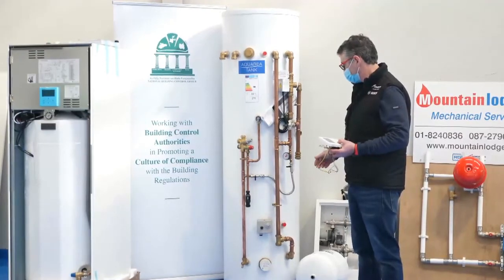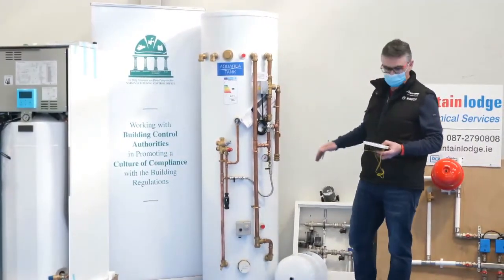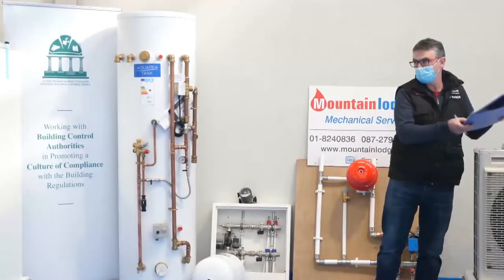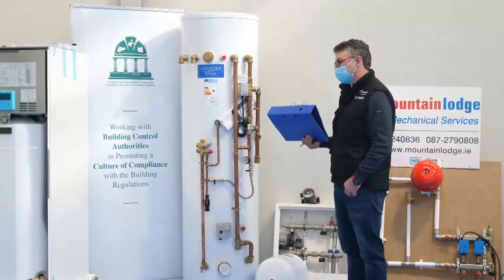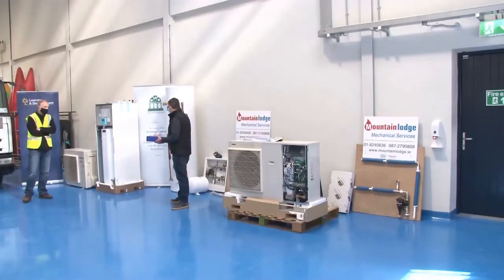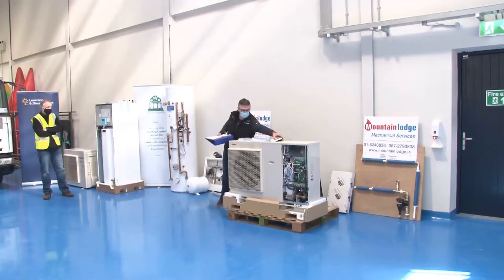And the second thing is there because we're heating hot water to max 52 degrees. At that temperature for prolonged periods, there is a chance of Legionnaires. Slight, but there is a chance that it will start growing on the inside of the cylinder, and if that grows in there, then you have a big hazard. So what most systems will do, they have the immersion here. It will be set on the programmer to bring on that immersion usually once a week at the same time every week.